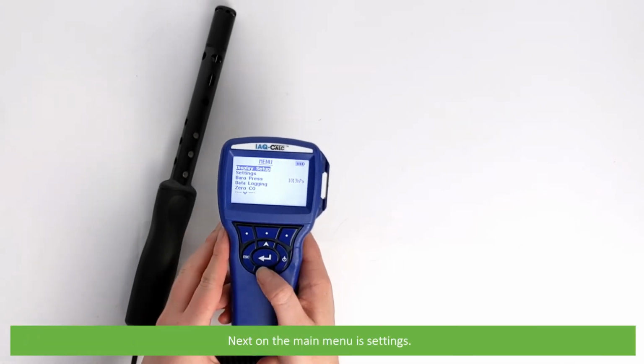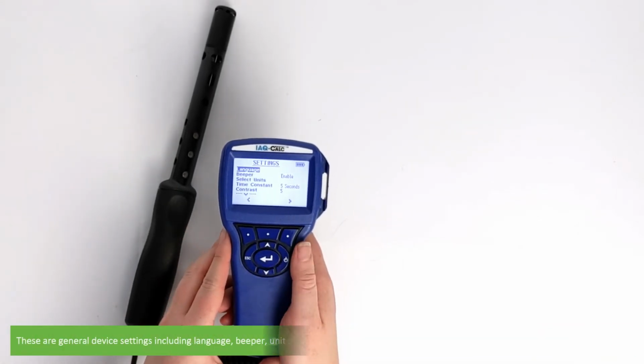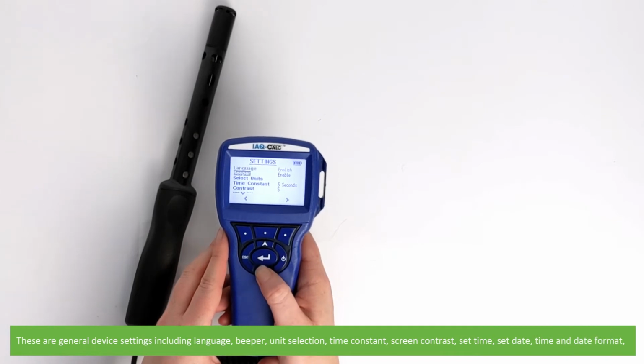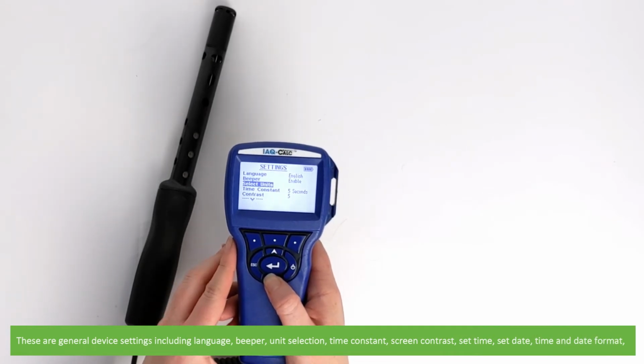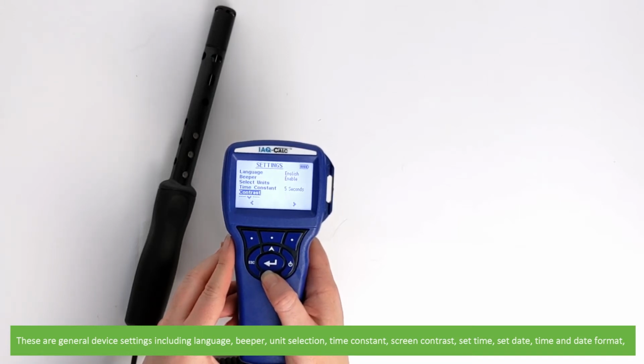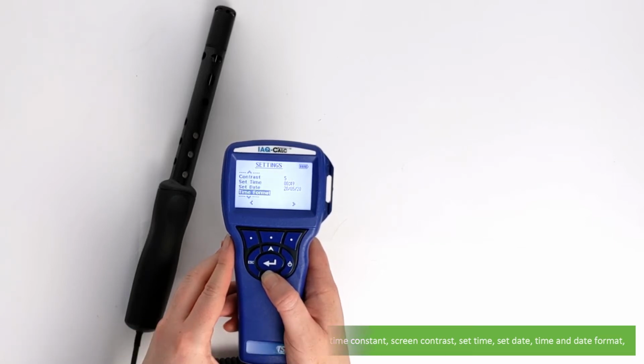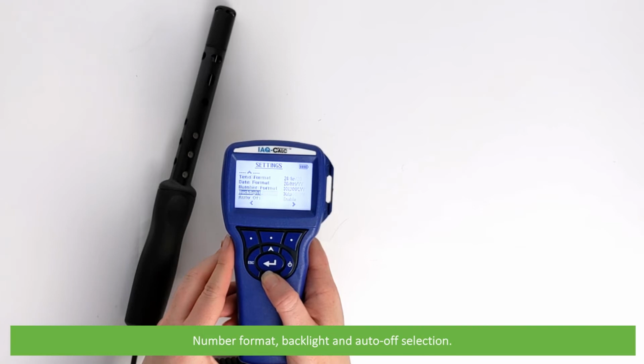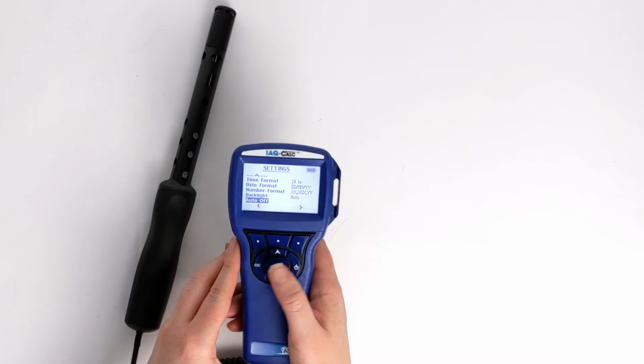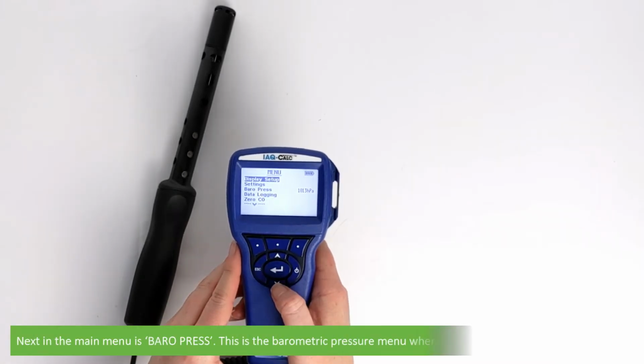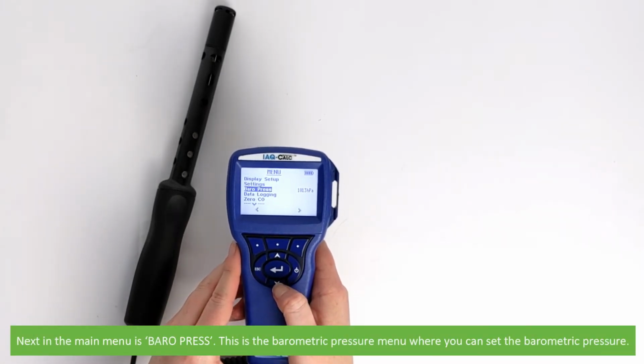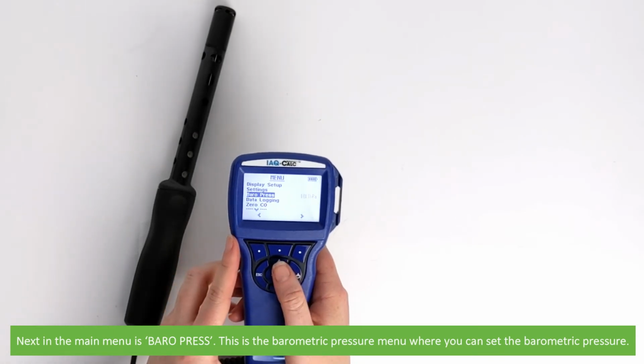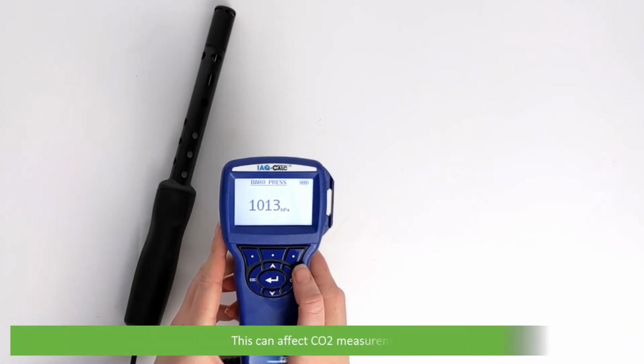Next, on the main menu, is Settings. These are general device settings, including language, beeper, unit selection, time constant, screen contrast, set time, set date, time and date format, number format, backlight, and auto off selection. Next on the main menu is Baropress. This is the barometric pressure menu where you can select the barometric pressure. This can affect the CO2 measurement.